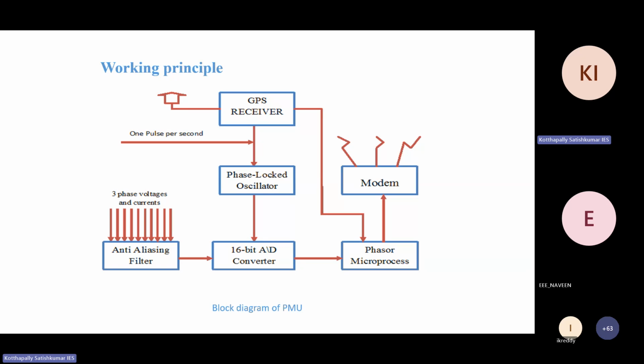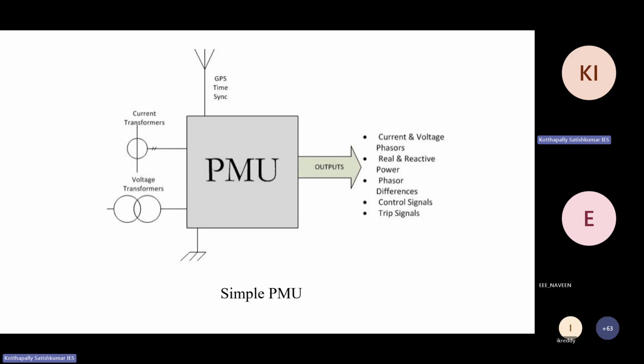Once the microprocessor processes the digital data, it gives the processed phasors, which are three-phase voltages and three-phase currents, and this data is transferred to the PDC. The PDC is like a server, placed at control centers such as the state load dispatch center, regional load dispatch center, or national load dispatch center. The data from the PMU is transferred to the PDC, which is nothing but a server.